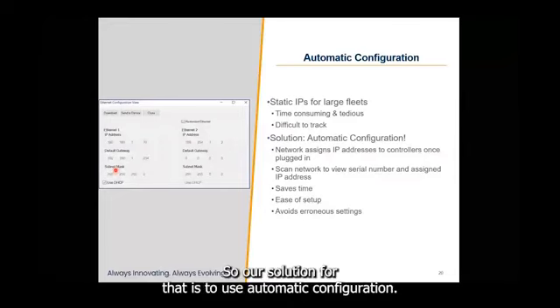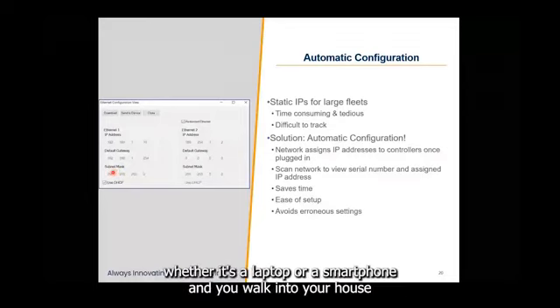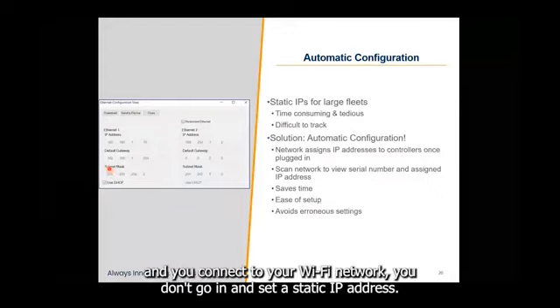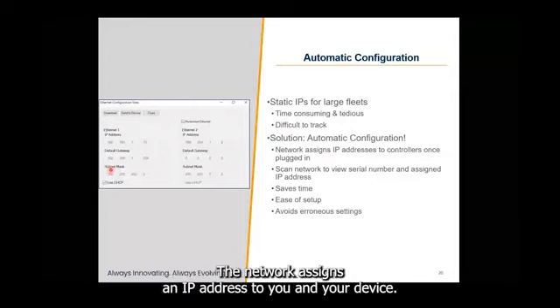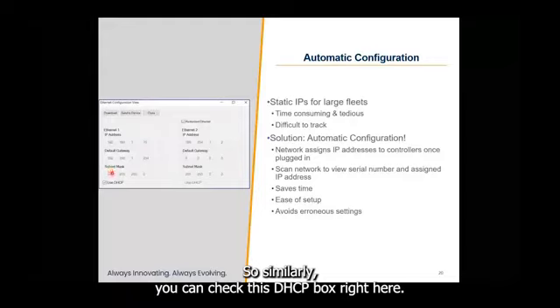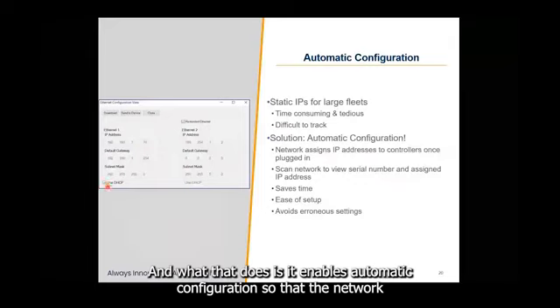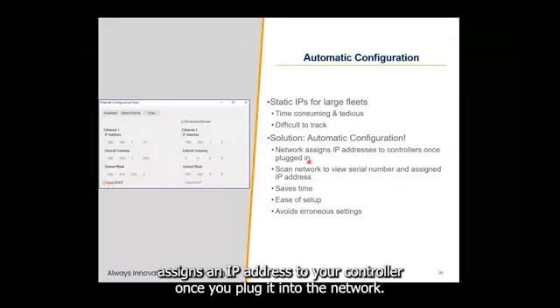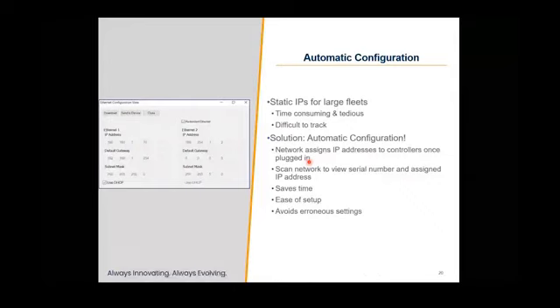So our solution for that is to use automatic configuration. If you think about it, when you buy a communications device, whether it's a laptop PC or a smartphone, and you walk into your house and you connect to your Wi-Fi network, you don't go in and set a static IP address. The network assigns an IP address to your new device. Similarly, you can check this DHCP box right here. What that does is it enables automatic configuration so that the network assigns an IP address to your controller once you plug it into the network.